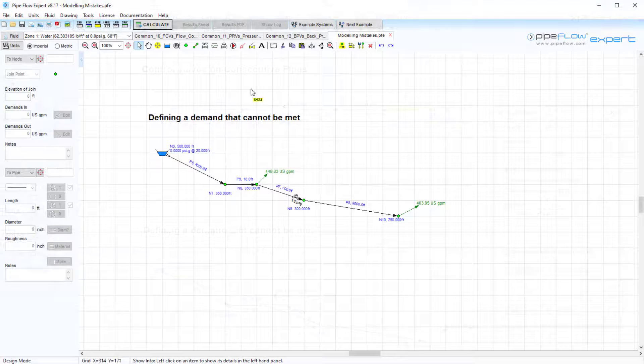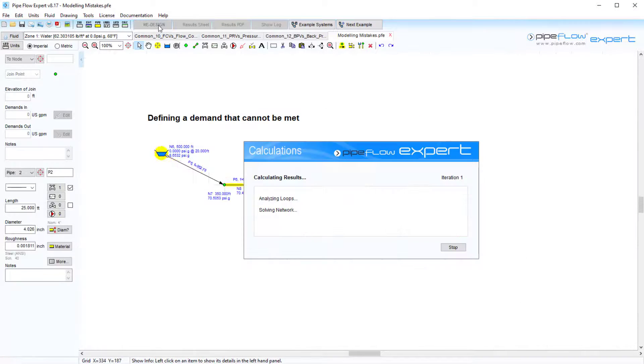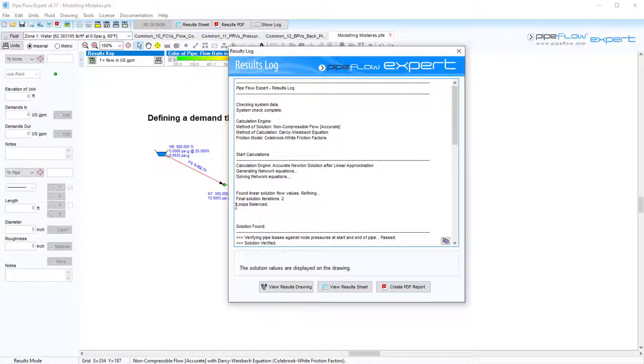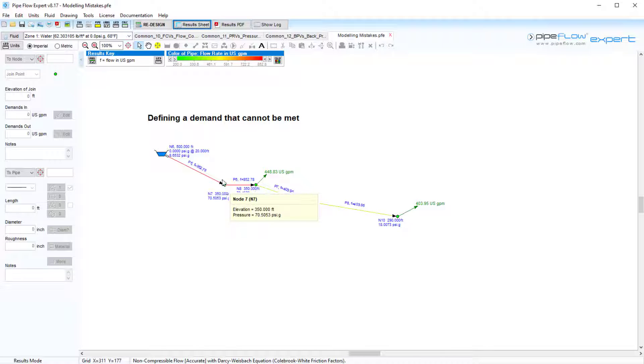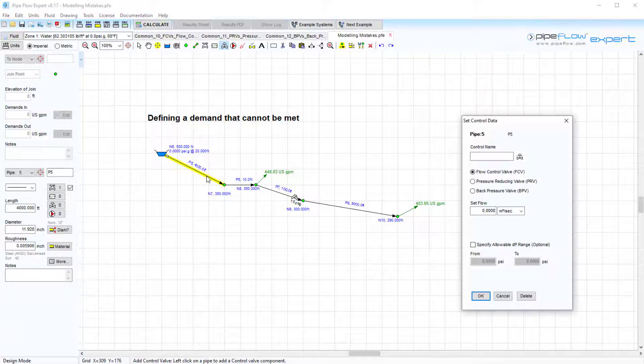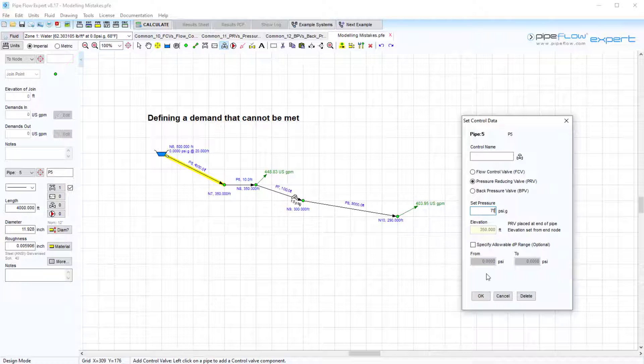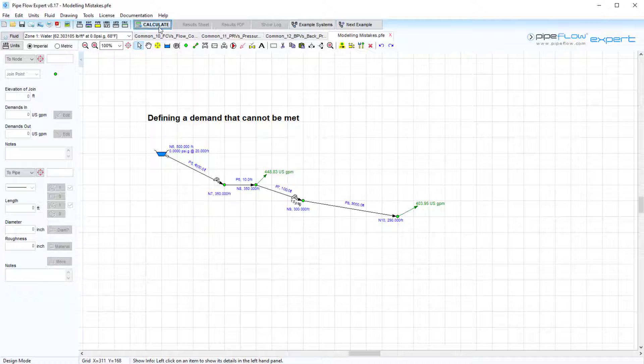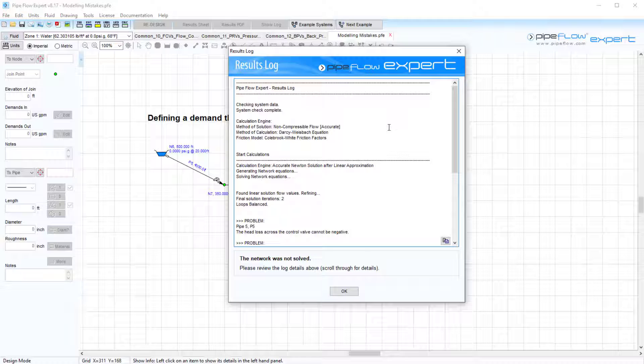Another common issue is when a control valve has been set to a demand that cannot be met. Looking at the PRV example again, we saw that the maximal pressure at the node was around 70 psi. If we set the PRV pressure setting to be higher than the maximal pressure, say 75 psi gauge, then the system will not be solved, and this is identified in the log here.